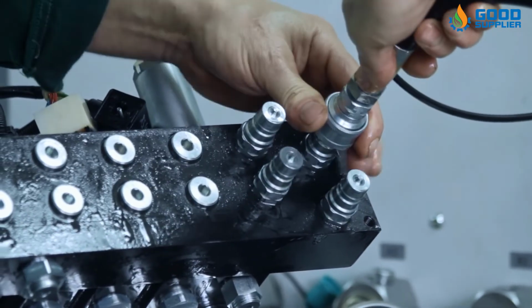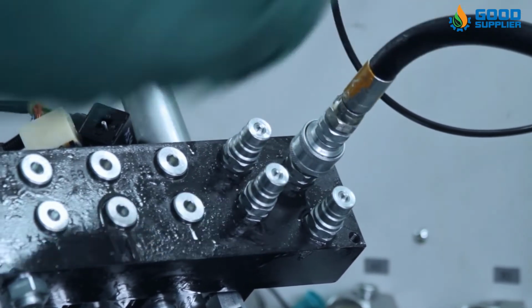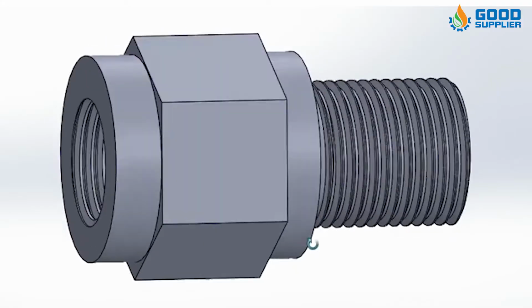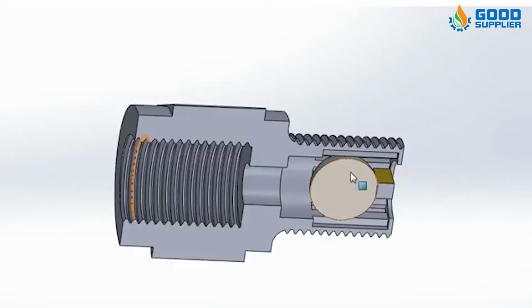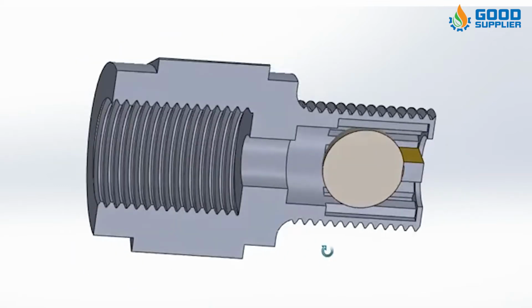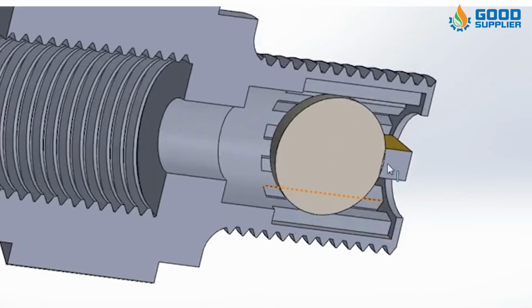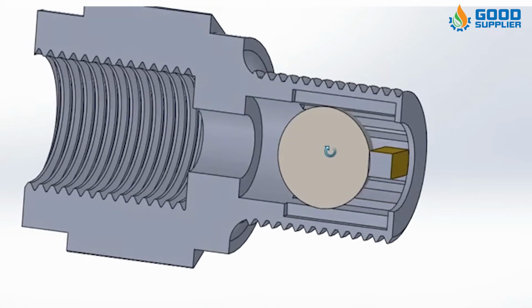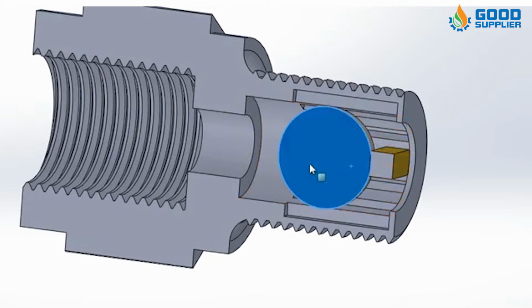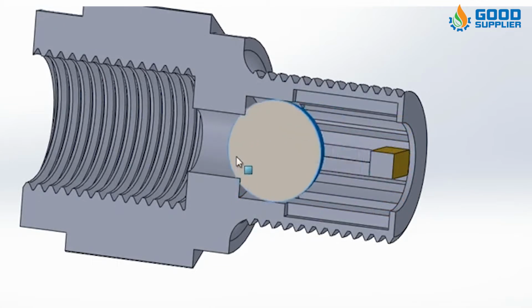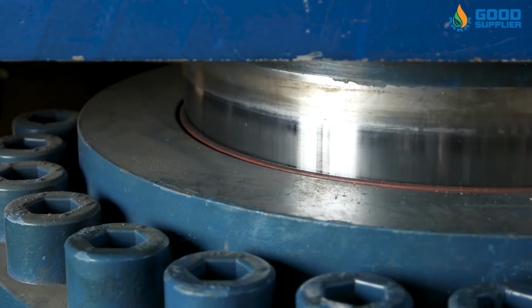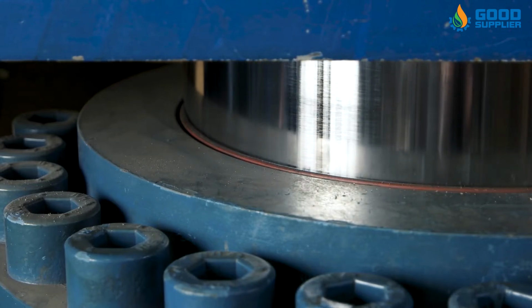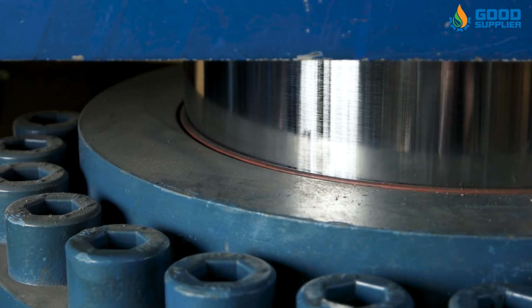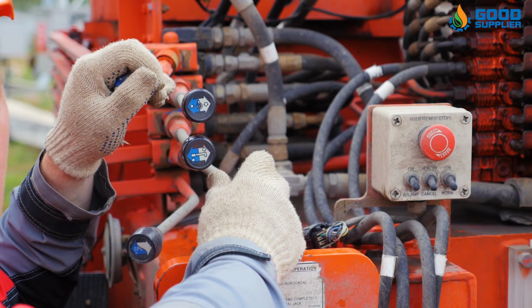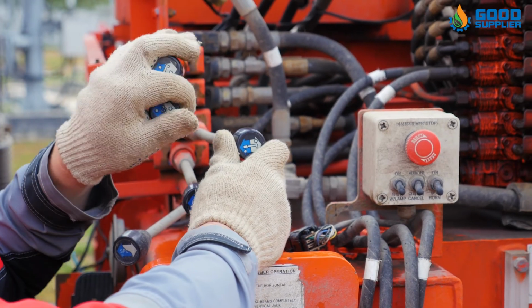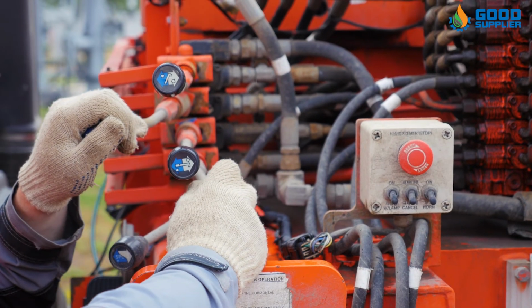Only a part of the liquid passes through the heat exchanger. Therefore, the flow rate depends on the opening pressure of the hydraulic check valve and is less affected by the total flow. The check valves with higher opening pressure are also used as low-pressure relief valves. There is no essential difference between the structure and function of the two. Hydraulic check valves can be divided into the one-way screw-in type and plug-in type according to the different installation methods.